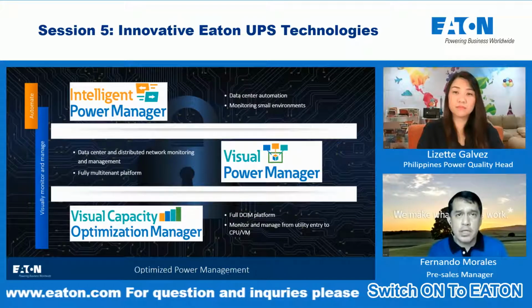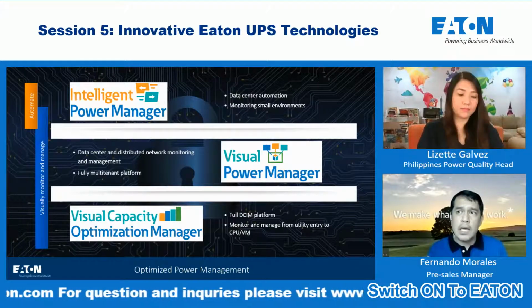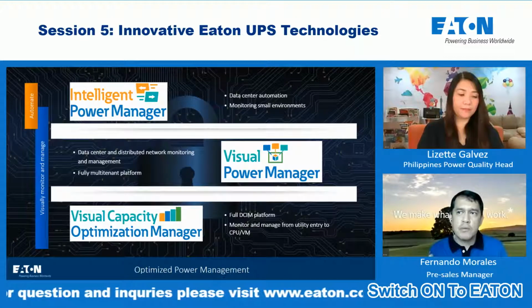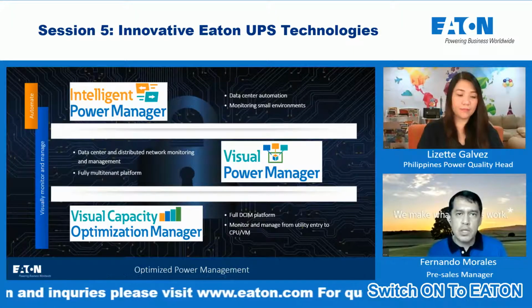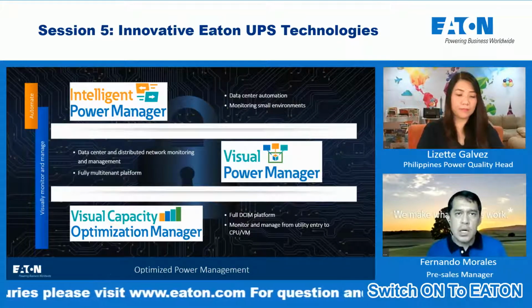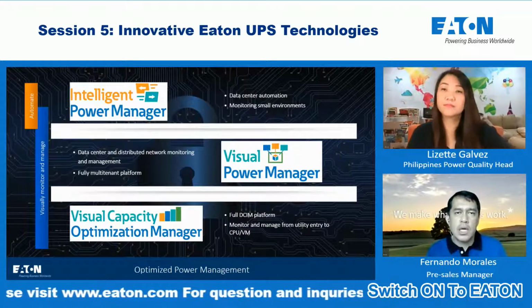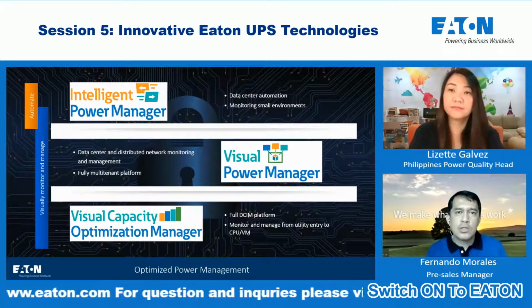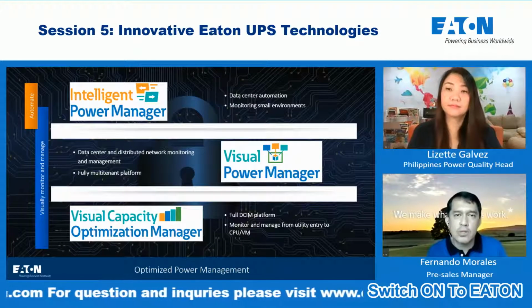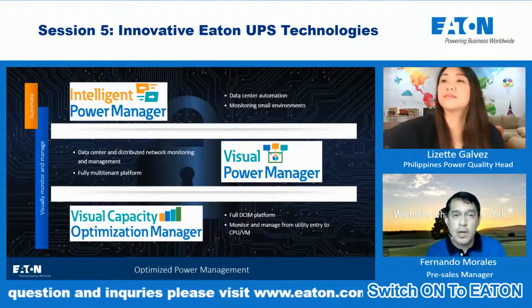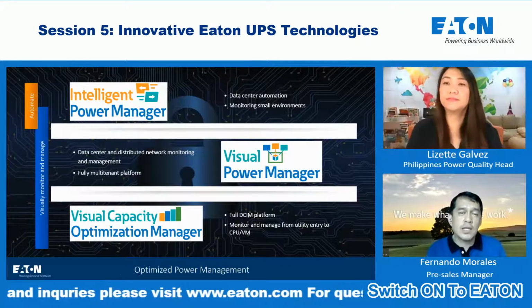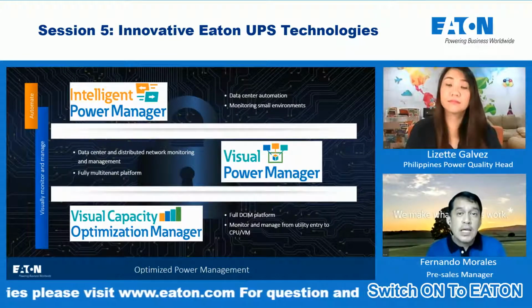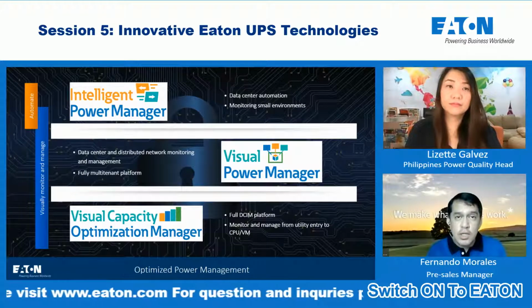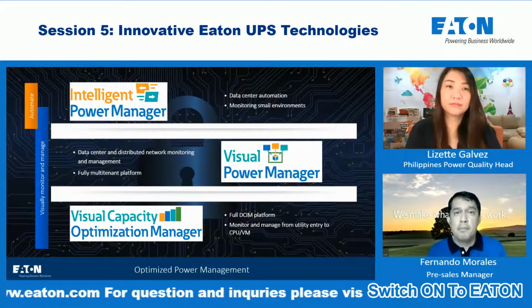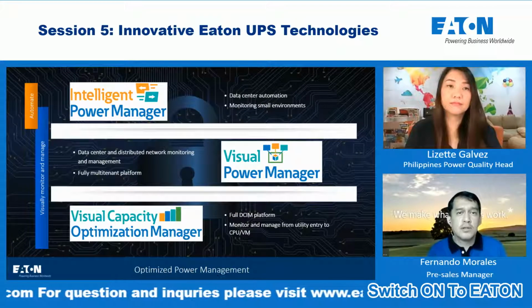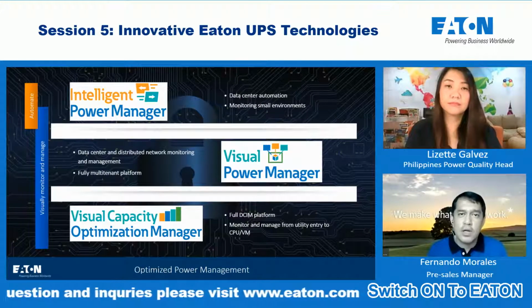With IPM, applying this for an IT environment, we can do automation. For example, we can program IPM so that after 5 minutes of a power outage, with the UPS still running on batteries, it can suspend non-critical servers or non-critical virtual machines. If we suspend or shut down these, the load of the UPS is reduced and its backup time goes up.